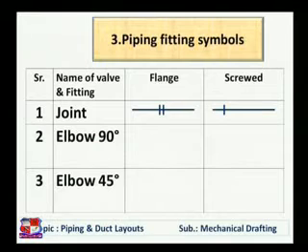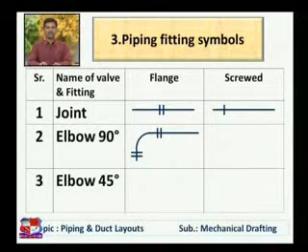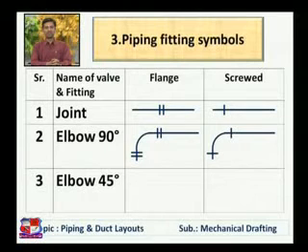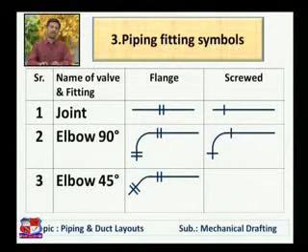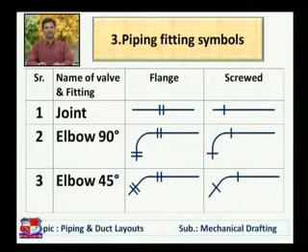To draw the symbol of a 90-degree elbow, its symbol is drawn with a bend. If it is a flanged joint, two lines are drawn; if it is a screwed joint, one line is drawn at two places to indicate a 90-degree elbow. A 90-degree elbow is used to connect two pipes which are at right angles to each other. A 45-degree elbow is also used — two lines meet at 45 degrees; flange has two lines, screwed has one line. It is used when two pipes are at a 45-degree angle.